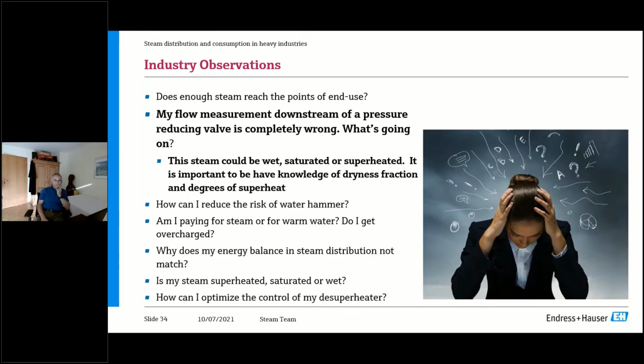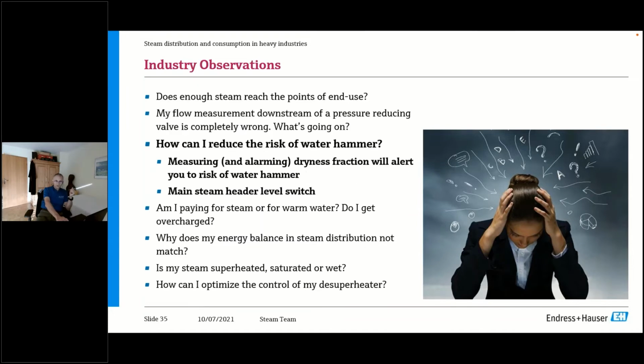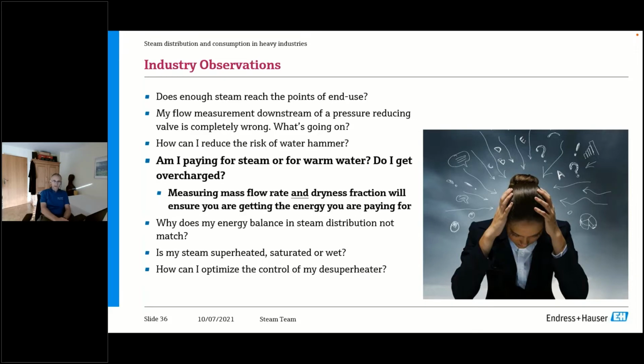And in general, this is so funny. Actually, in all parts of your system, you can have steam either superheated or wet. So it always makes sense to know degrees of superheat and the dryness fraction, because one of the two can be an undesired occurrence. So only if you measure it, you can control it. How can I reduce the risk of water hammer? Well, here measuring the dryness fraction provides you an alert and an early warning, so to speak. And also this main steam header level switch is very helpful here.